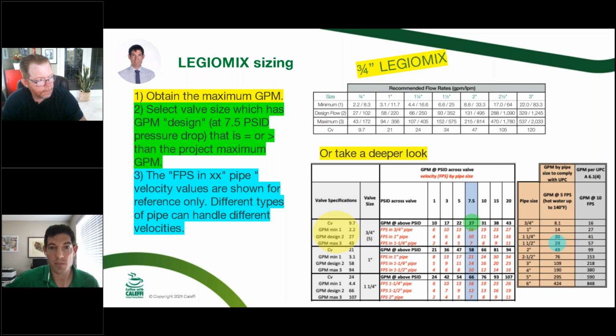If we want to take a deeper look, this next chart down here takes a minute to walk through, so I highlighted the different steps. First, we're going to look in the yellow shaded area for the minimum GPM. 2.2 is great. We were looking for 2 GPM, and if we've got the recirc hooked up to this too, we're going to be plenty over there. Design of 27, so all that looks good.